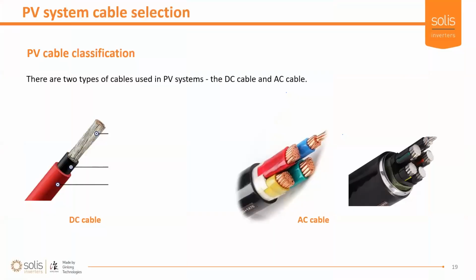Okay, PV systems have a DC side and an AC side. So that's the point of an inverter. It converts your DC to your AC. And the cable selection process is slightly different for each. On the AC side, we have two materials that can be used. Your copper being the better one, lower resistance and higher current carrying capacity. But you have to pay for that, so a bit more expensive. And then your aluminium cable, which I seldom see getting used, which is a good thing. Copper is just generally a better material to use.